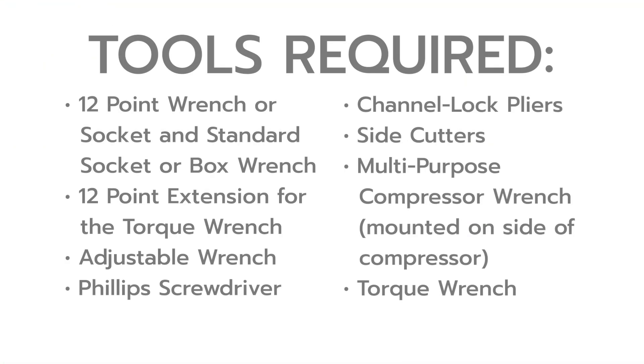Repairing a loose piston in a Corken vertical compressor requires the following tools: a 12-point wrench or socket and standard socket or box wrench, a 12-point extension for the torque wrench, an adjustable wrench, a Phillips head screwdriver, channel lock pliers, side cutters, the multi-purpose compressor wrench which is mounted on the side of the compressor, and a torque wrench.